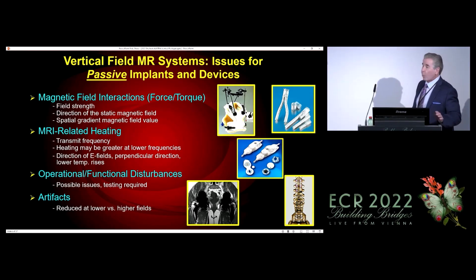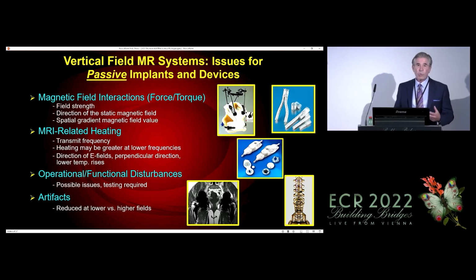What our group reported nearly 20 years ago is that heating can be substantially greater at lower frequencies, depending on the length of the implant. And that's not intuitive in many instances, unless of course you're an MR physicist, then you understand that entirely. With regard to these vertical field systems, the direction of those E fields is perpendicular, entirely different than a horizontal bore system. What has been reported in both passive and active implants is that the heating is substantially less.